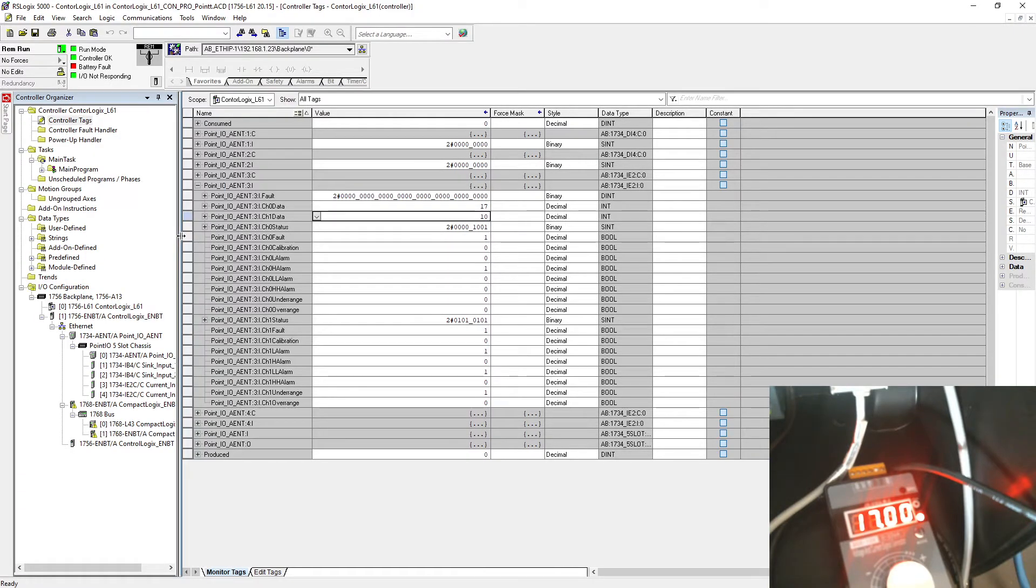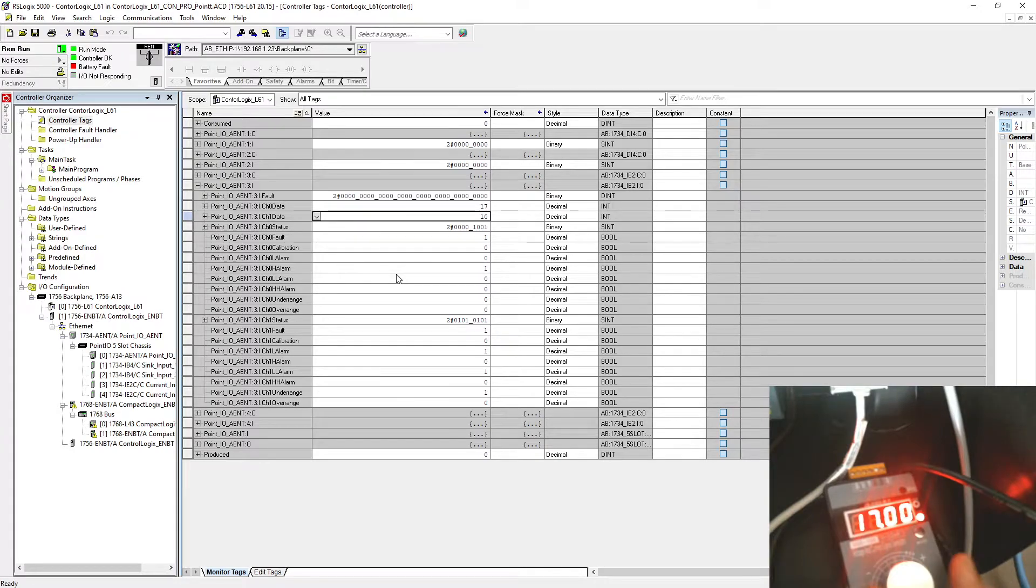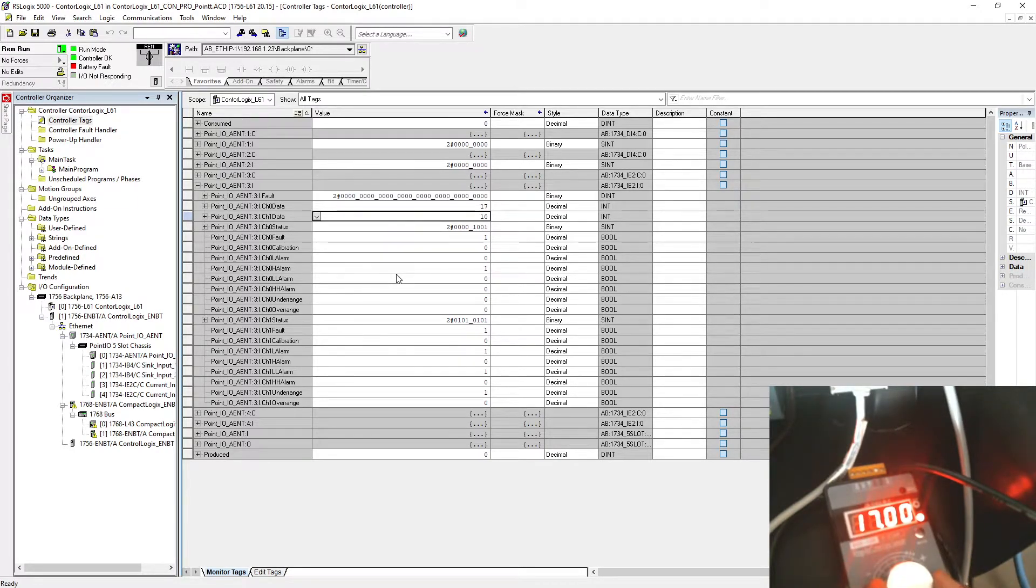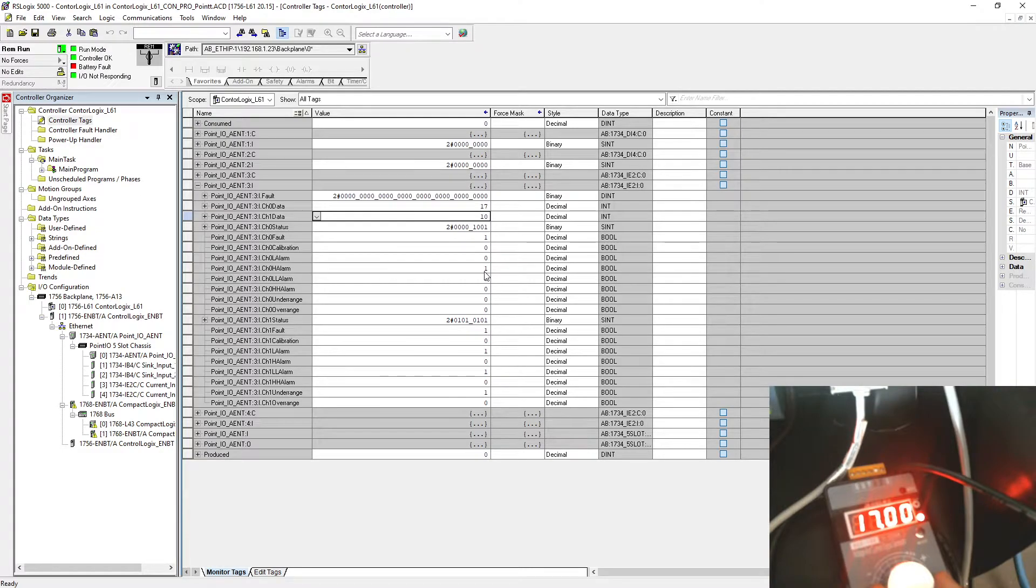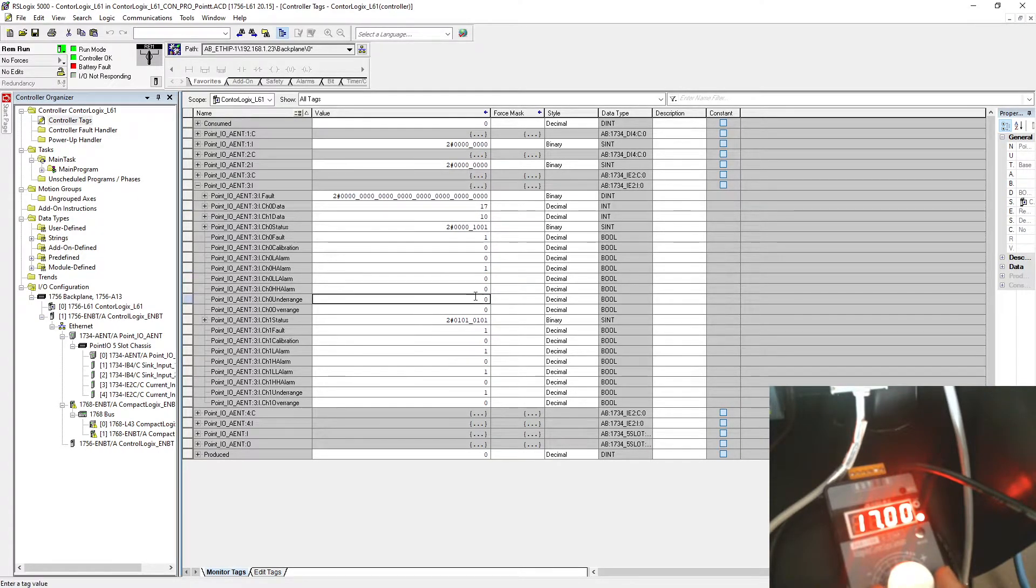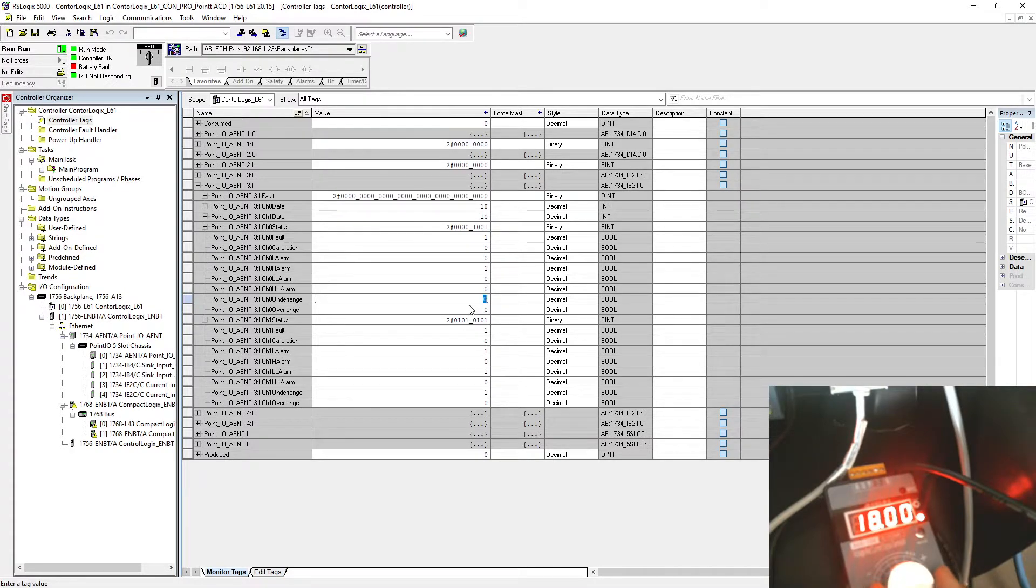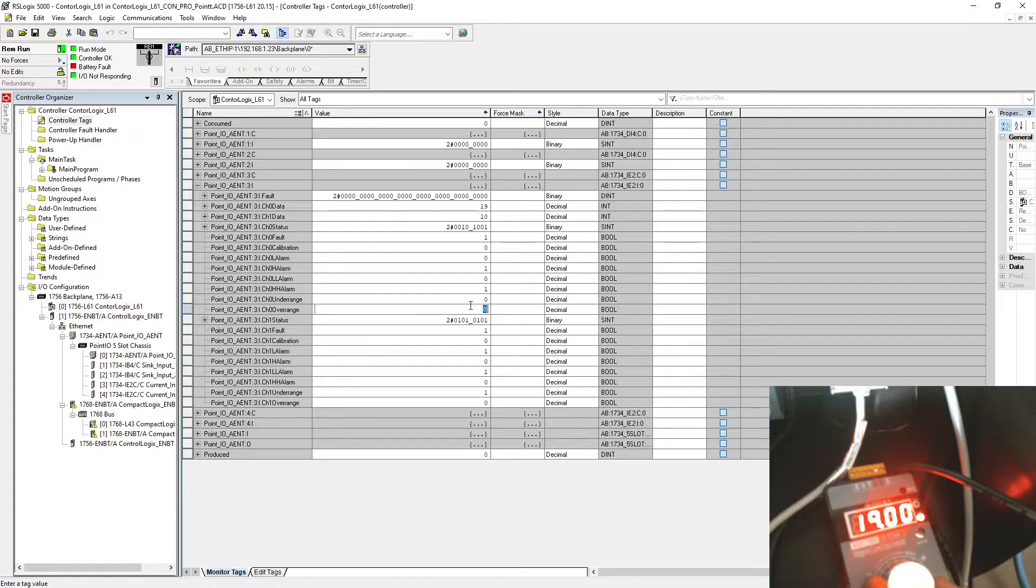Keep watching this: that's 15, 16, 17. Let me just move this more on this side. 17, 18. As you can see, right now I'm at 16, and when I go above 16 my high alarm turns on right there. And when I'm going to be above 18, my high-high alarm will turn on.